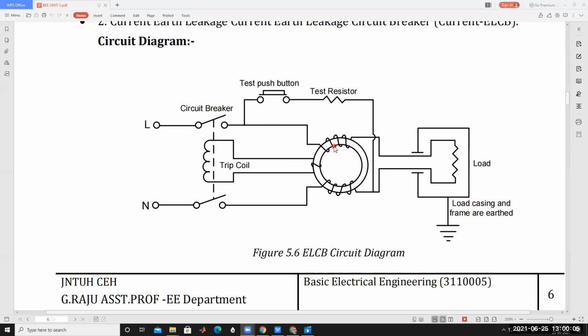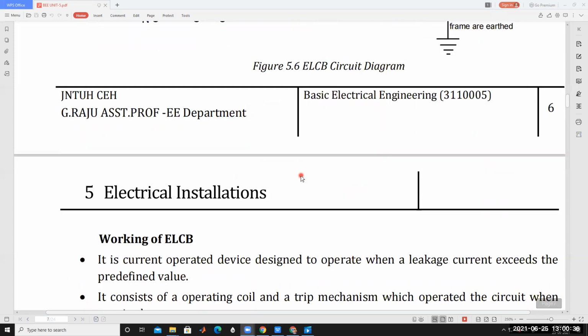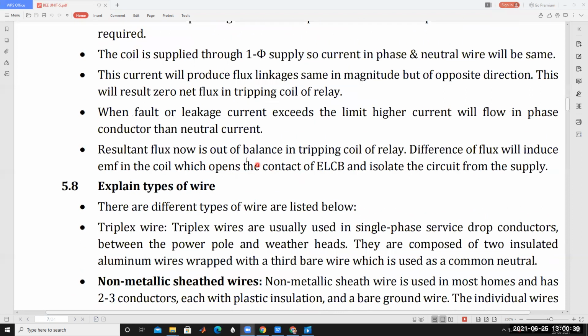Because of that, whatever flux is generated here can be opposed by this coil. The flux direction here is in this direction, and the flux direction here is in the opposite direction. Then the resultant flux will be 0. Because of the 0 flux, the 0 flux is induced on the tripping coil. That's why the tripping coil is not activated. Under faulty conditions only, the tripping coil is activated.